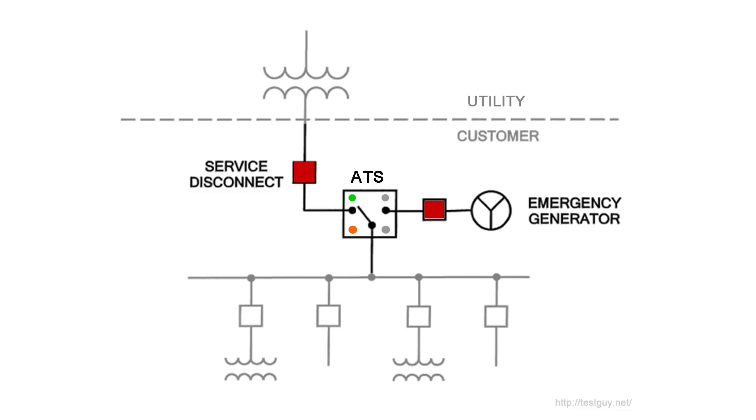Step 3. Simulate a utility outage by opening the normal source circuit breaker. The delay to engine start timer begins its timing cycle. After the timer has completed its timing cycle, the engine start contacts close to start the generator.